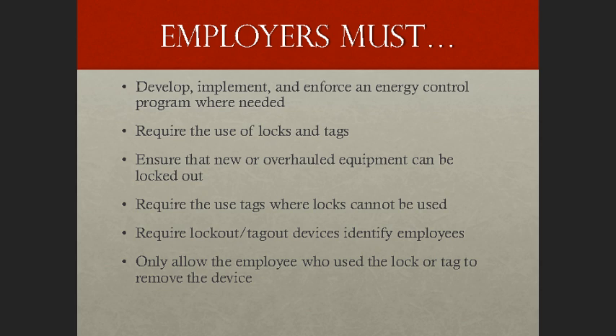Employers must do the following whenever Lockout Tagout standards apply to their industry. First, they must develop, implement, and enforce an energy control program. Employers must require the use of locks and tags where standards apply, and ensure that new or overhauled equipment can be locked out. They must require the use of tags where locks can't be used, and require Lockout Tagout devices to identify the employee — whether by picture or name — so it's clear who is doing the work.